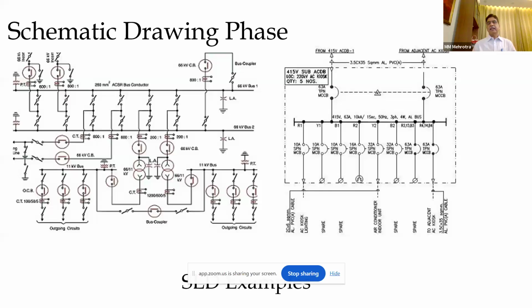On the right hand side, I have shown you a small depiction of a single phase distribution circuit. What happens? The supply is coming from three phase, that panel which you had seen. It is being distributed to various sides, right? Now each MCB is showing one circuit. Each circuit will have a certain number of points. Usually it's around 7 to 10 points in each circuit. So they will take care of the loads.